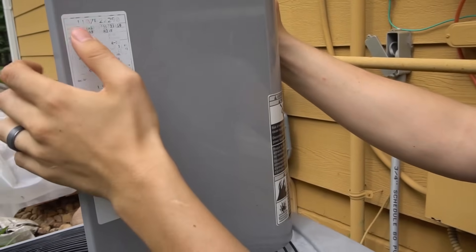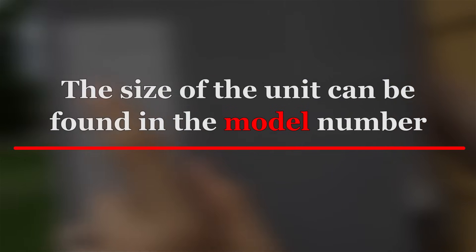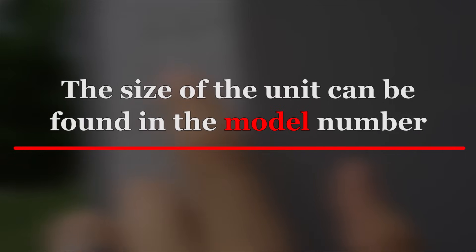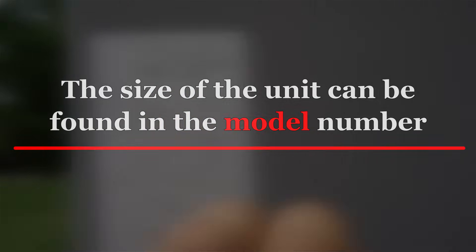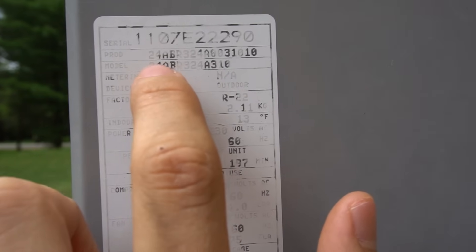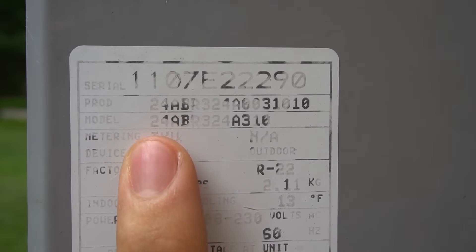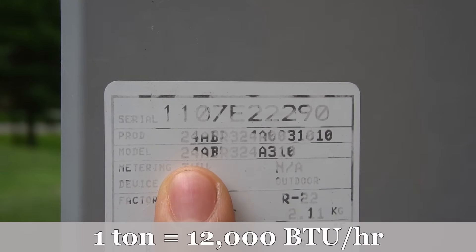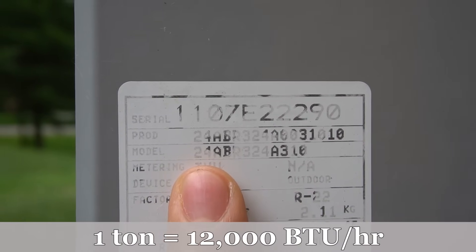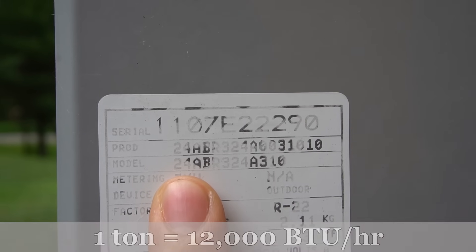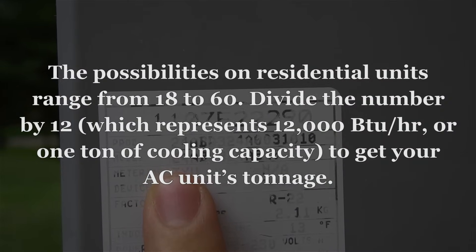You're going to look for a series of two even numbers, which are usually going to be either in the beginning or in the middle. So in my case, it's actually kind of weird. It's in the beginning and the middle, 24 right there. That will be the tonnage of your unit. And what this number means is basically one ton of cooling capacity. So one ton of cooling capacity is 12,000 BTUs per hour. It'll go 12, 24, 36, 48 for one ton, two ton, three ton, four ton.